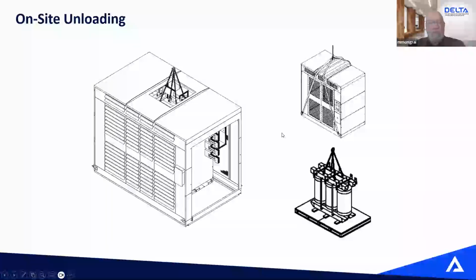If you have any disassembling work to do on the core and coil or the enclosure, then you can do it and bring that in the room. We can also provide a service of shipping the transformer disassembled. So we'll ship the core and coil in one crate, all the buswork disassembled on pallets, and the enclosure can be shipped either fully assembled or disassembled, laid flat on a skid.